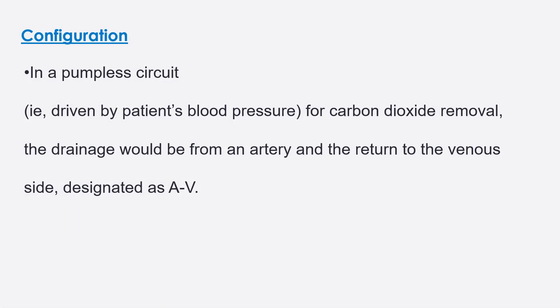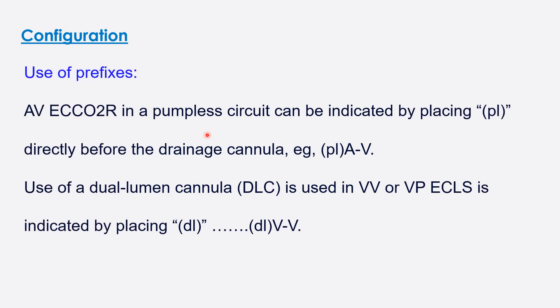In the AV circuit, blood is driven by the patient's own blood pressure for CO2 removal. Drainage is from the artery and return is to the venous side, so it is designated as AV. A pumpless AV extracorporeal CO2 removal circuit is indicated by placing PL directly before the drainage, making the cannula PL-AV. Use of a dual-lumen cannula in VV or VP ECLS is indicated by placing DL before the configuration, such as DLVV.